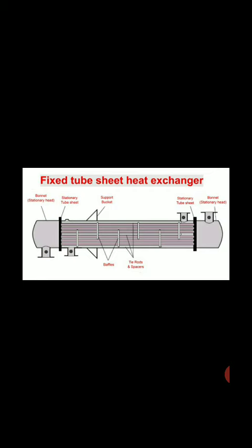The fixed tube heat exchanger is applicable only where the temperature difference between the shell and tube is small. When the temperature difference between the shell and tube is high, there is always a possibility of damaging the tube or shell due to higher temperature differential stresses.